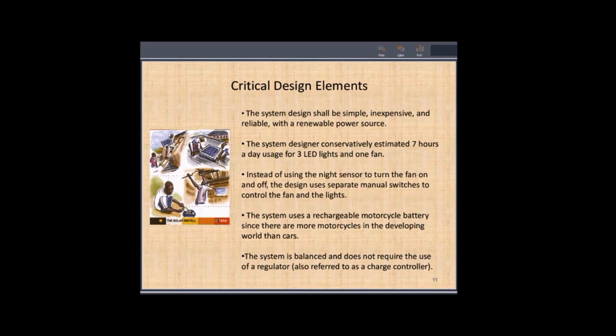So having manual switches and teaching people that. Think about solar electric: we have a battery also, so we're charging the battery. If you have a control on the system, which we didn't, and that turns it off, a lot of times you're discharging the battery too much. Because the people who design those control systems, I don't know how else to put that, they don't think that people can think for themselves, so most of the time, especially with small systems, they don't let you change the settings. And so by using the controller as an off switch, it usually tends to discharge the battery too much and reduce the life of the battery.